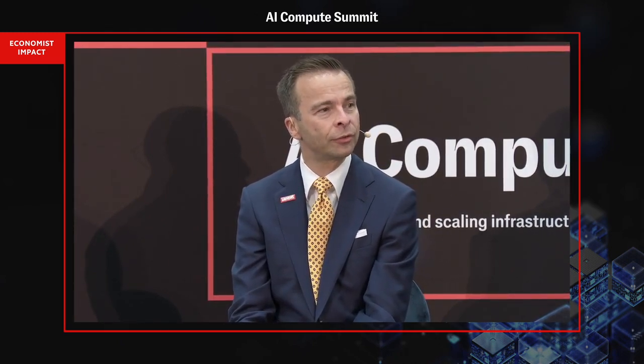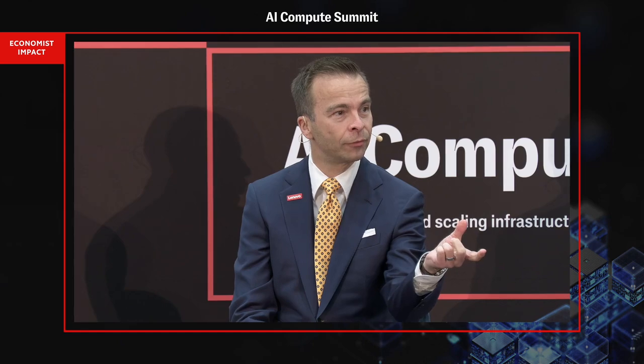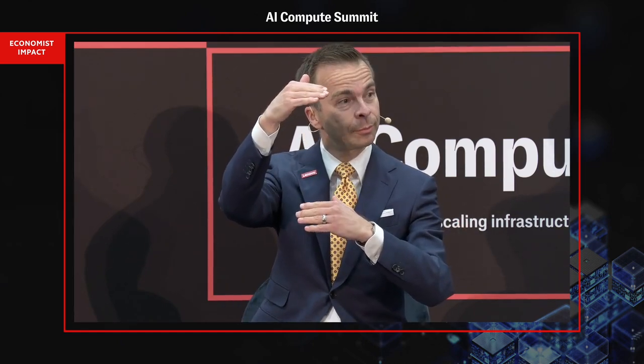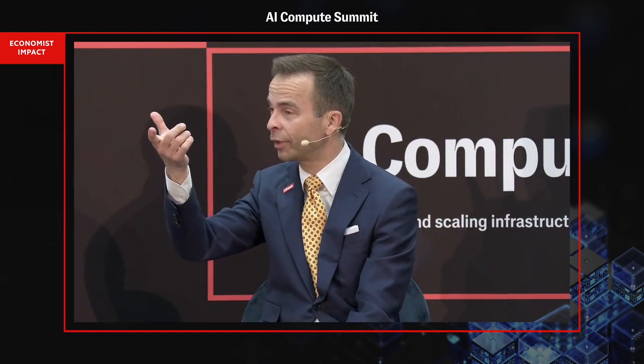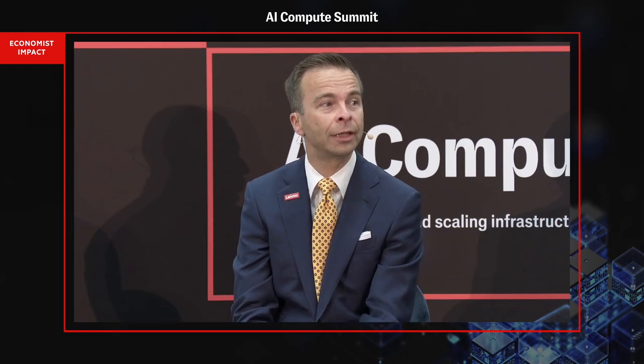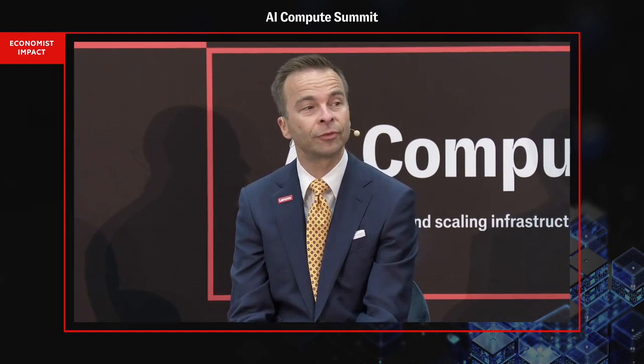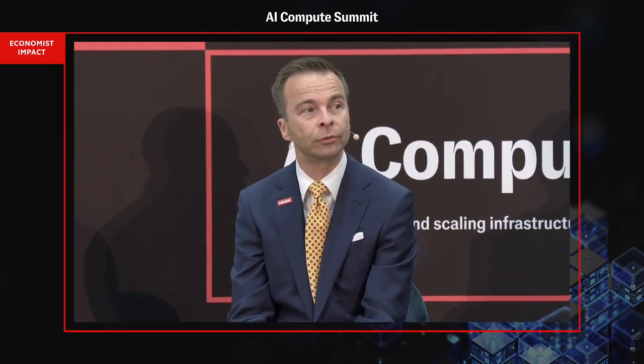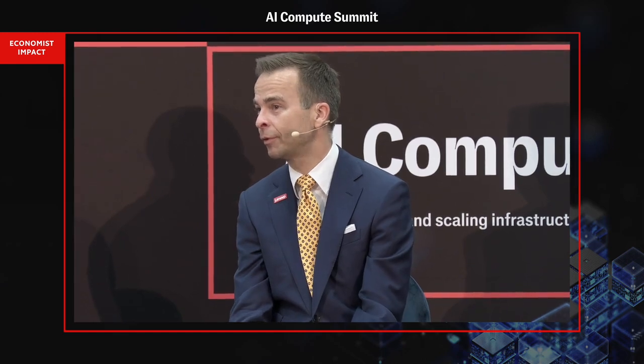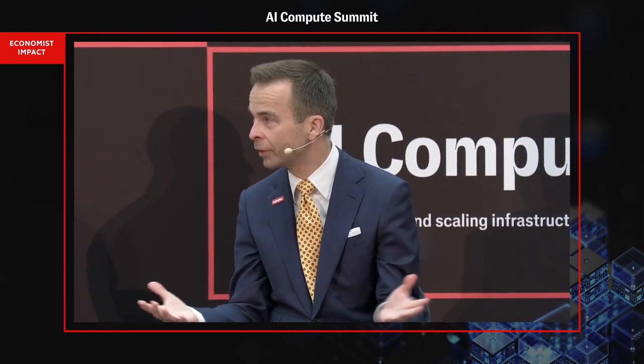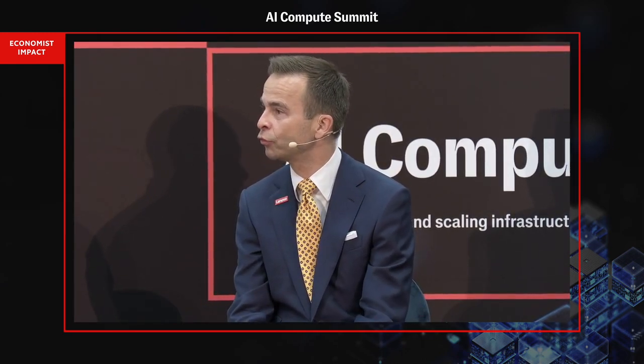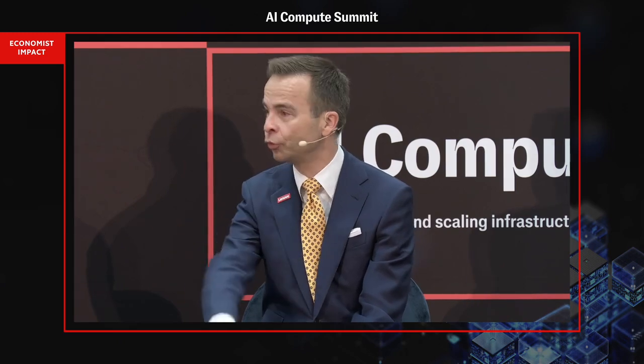If you put this together, you have a factor of 30% savings on the fans, and on top of that, for the total bill, another 30% savings. So you can do the math and easily get to 40 up to 50% total energy savings by moving to liquid. And that, depending on your CO2 footprint, reflects on your sustainability story—the first thing is to reduce energy consumption.